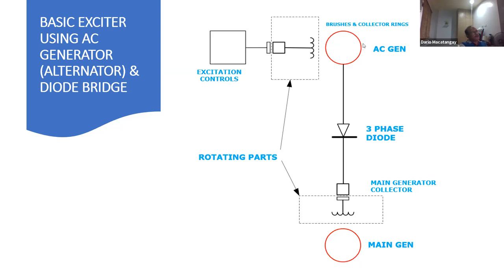So now this portion here is stationary, and then again, you need those excitation controls to ensure that enough magnetic field is provided in the generator, either to boost the voltage or to reduce the voltage output of the main generator. Just remember that excitation has to do with the amount of voltage that you need to put into the system. When you're talking about voltage, it's about excitation. When you're talking about power, megawatts, it's about the amount of energy passed from the turbine to the generator. So those are two separate things.